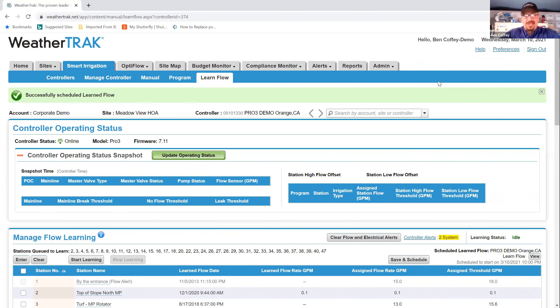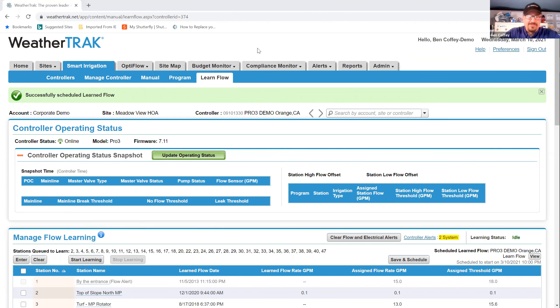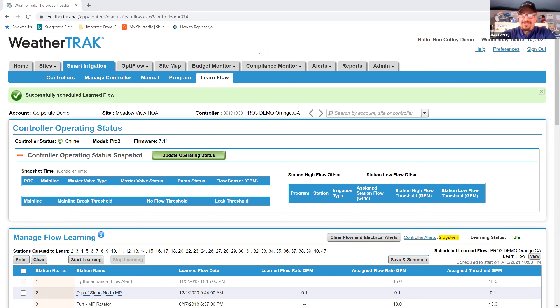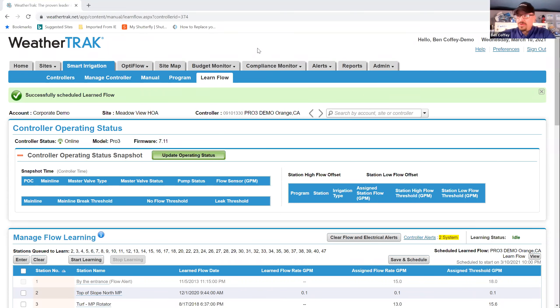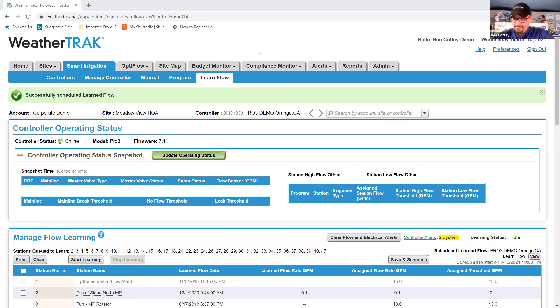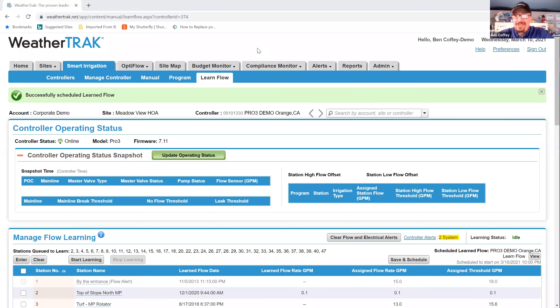And that is once I hit save and close, that goes into the queue and it tells you right here that I have successfully scheduled to learn flow. And if I want to view that event, I can just come over here and click that view and it'll take me to the details of when that's all going to go down. Make sense? Questions on any of that? Let's check the chat box. Steve Ray says, how do you find broken heads or small leaks if they are only adjusting your flow rate slightly? They have to be outside of that tolerance. They have to break that 20% rule to be big enough to have an automated response. So I think that this is always justification for wet checks. Nothing's ever going to catch sprinklers running in the wrong directions.